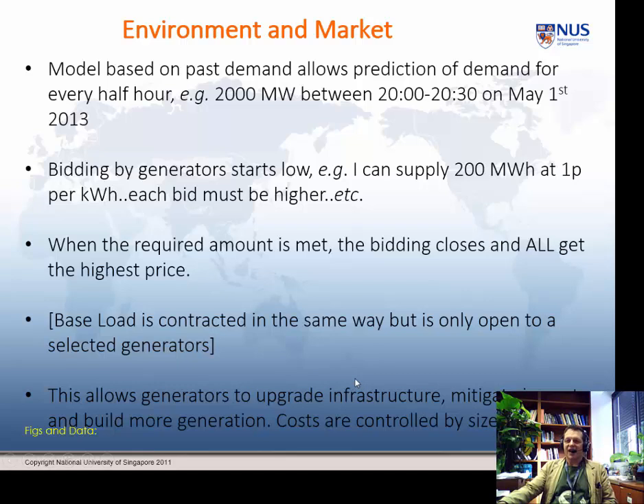Okay, so how does the model work for electricity? Basically, there's an auction. It starts a couple of days before the actual power is required, and they have a model based on past demand. It sets your predicted demand for every half hour, and the generators bid, saying, okay, I can supply 200 megawatts at 1 cent a kilowatt hour or whatever. But each bid subsequently must be higher. When the required amount is met, the bidding closes and everybody gets the highest price it got to.